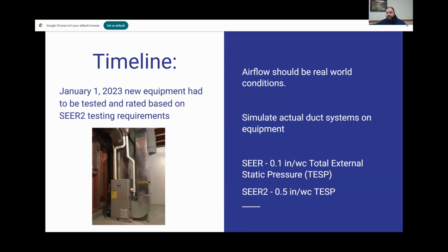It boiled down to, in the bottom right corner of the screen here, it says SEER was running the equipment with a 0.1 total external static pressure. So the total external static pressure is the difference in pressure between the blower cabinet on the furnace and the discharge air of the furnace.